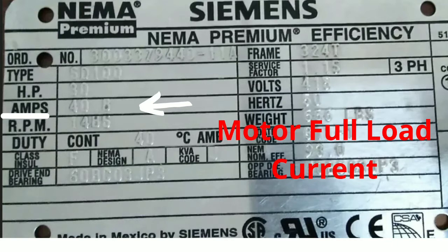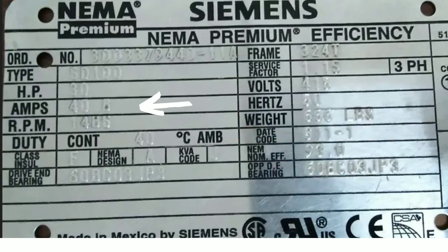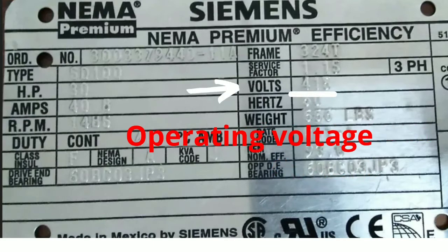Motor operating voltage is one of the most critical pieces of information on the nameplate. Connecting the motor on lower voltage causes the motor to draw higher current than it's rated, while connecting the motor on a higher voltage causes the motor winding insulation to break down and the motor to burn out.